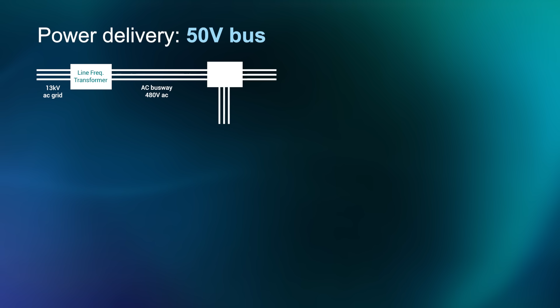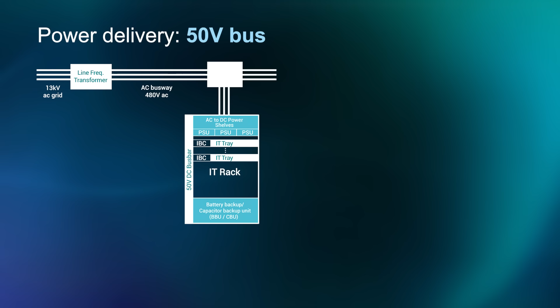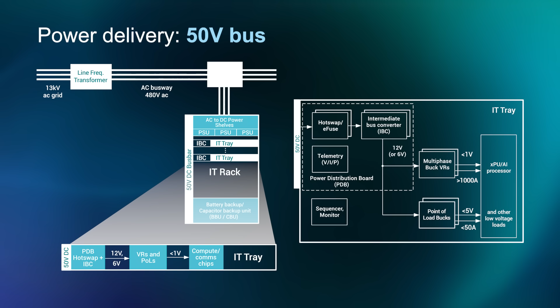Now, the next evolution of power delivery introduced a 50-volt bus. This is sometimes called a 48 or 54-volt bus, since the nominal voltage may vary, but the voltage is generally somewhere between 40 and 60 volts. In this architecture, power is converted from AC to approximately 50 volts through the PSUs located on power shelves. The 50-volt bus bar goes down the back of the rack to distribute power to the IT trays. Inside the tray is a power distribution board, or PDB, which contains an intermediate bus converter. That IBC converts power from 50 volts down to 12 or 6 volts. This power is delivered to processors through multi-phase VRs. This architecture often includes battery or capacitor backup units in the rack.